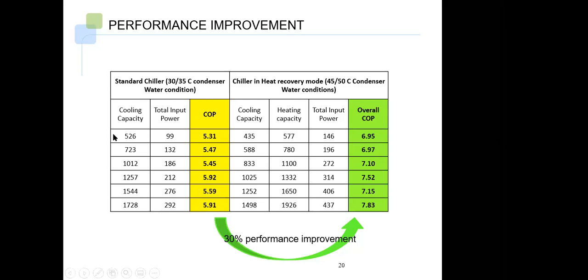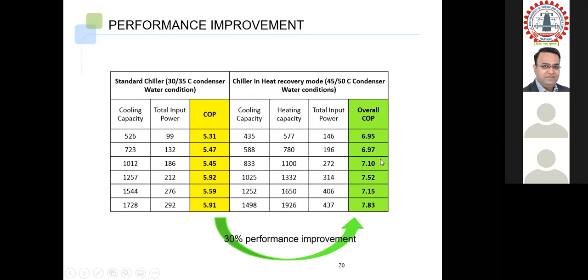I just picked up some examples for different cooling capacity of chillers, which is mentioned here, in kilowatts of cooling capacity. What is the total power input and what is the COP of a chiller, individual chiller. But if we recover the heat, on the right hand side, from this chiller on the heating capacity, our net COP or net efficiency improves at least by 30% from the standard one when we use both sides of the heat. Means at one side we are picking up the heat from the indoor space, and second, instead of rejecting this heat to the atmosphere, we are beneficially using this heat for the boiler or hot water purposes. So we use both sides of the heat, and then the efficiency of the system improves significantly.